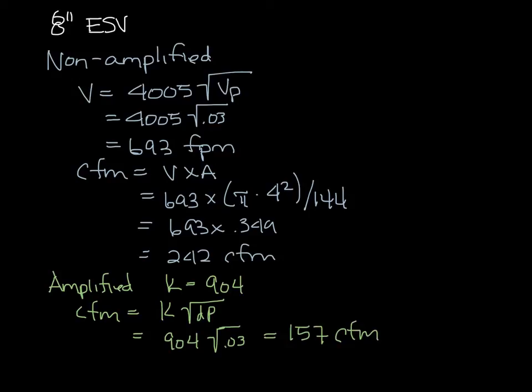So without the amplified signal, you could read down to 242 CFM versus 157 CFM for the amplified signal. So we're often asked how low our VAV boxes can go, but the answer depends on a couple things.